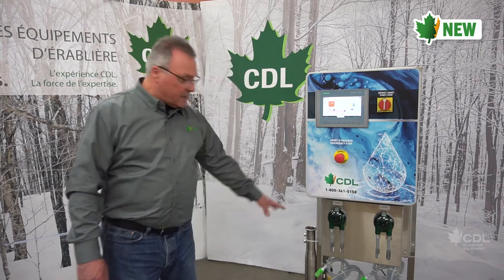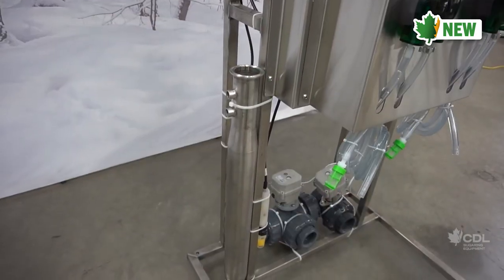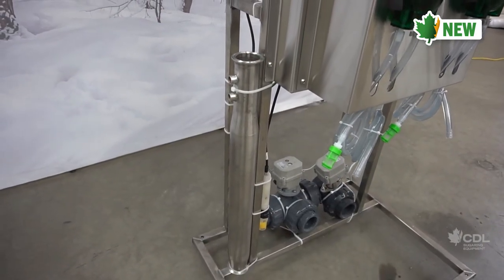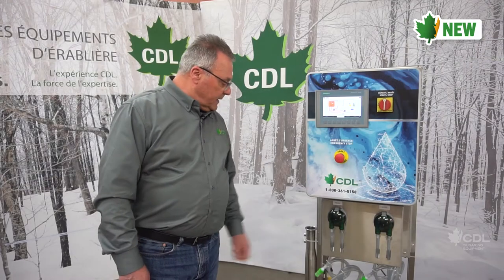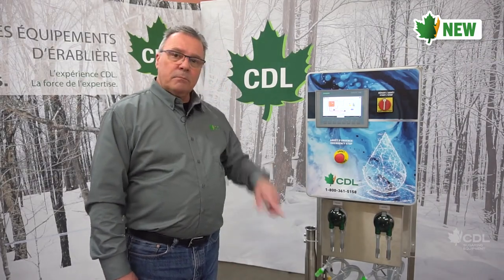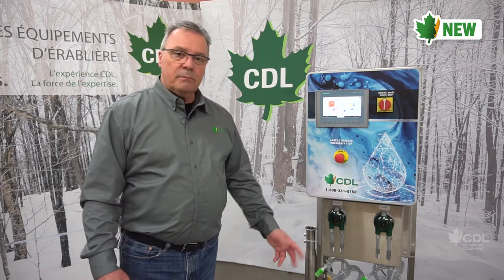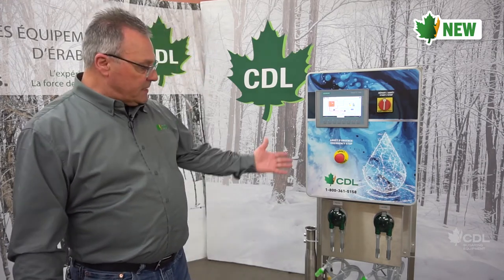You also have here a static mixer, which is tied to the equipment. As water is being circulated through the system, it enters the static mixer, and then it mixes either with the citric acid or pH buffer. So it's very simple equipment.